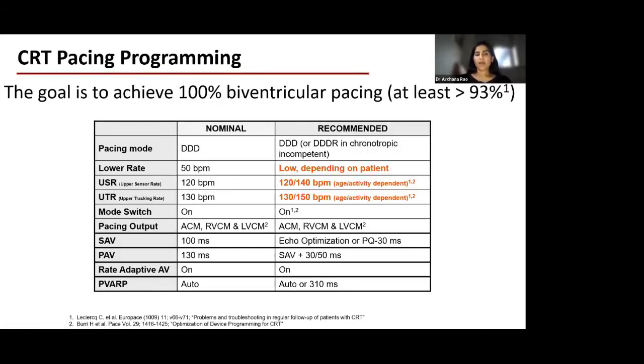So, CRT pacing programming. We'll go through this in a little bit of detail because this is an important slide. The goal of CRT pacing is to achieve 100% biventricular pacing, so at least 95%. Now, in order to do this, you need to ensure that your LV lead placed has a decent threshold, and that threshold is not too close to twitch threshold. Because if you accept high thresholds, and the patient then has twitch at lower thresholds, then there's going to be a problem because you're not going to be able to pace with an adequate safety margin.